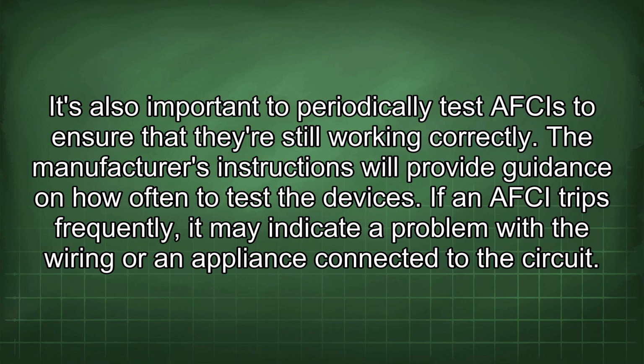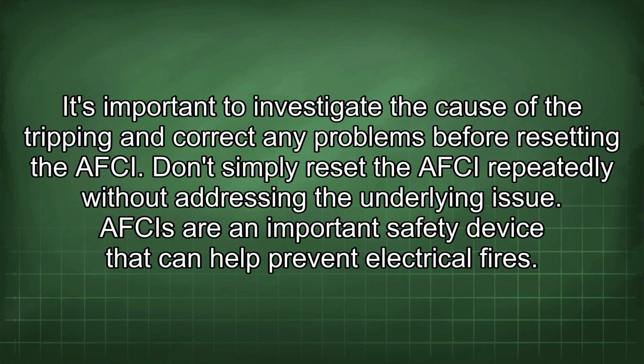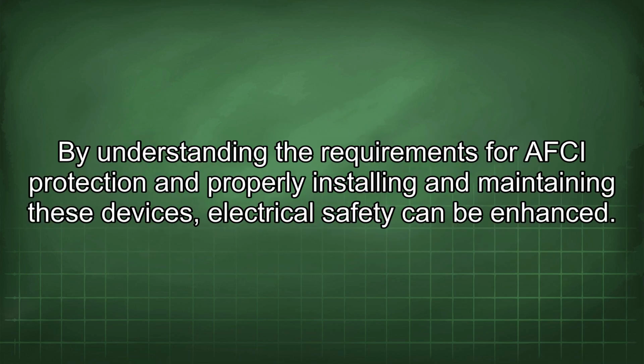If an AFCI trips frequently, it may indicate a problem with the wiring or an appliance connected to the circuit. It's important to investigate the cause of the tripping and correct any problems before resetting the AFCI. Don't simply reset the AFCI repeatedly without addressing the underlying issue. AFCIs are an important safety device that can help prevent electrical fires. By understanding the requirements for AFCI protection and properly installing and maintaining these devices, electrical safety can be enhanced.